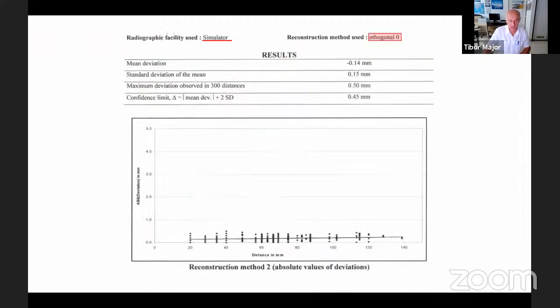And this is the result. Here you can see the mean deviation of the real coordinates and the calculated coordinates is around 0.1 millimeter, and the maximum deviation was only 0.5 millimeter, less than 1 millimeter. This means with this imaging and with this reconstruction software, the coordinates of the source positions can be determined very accurately.